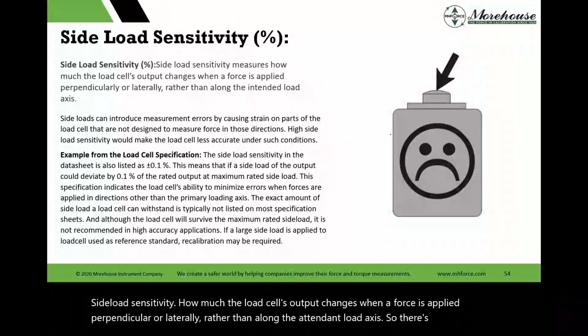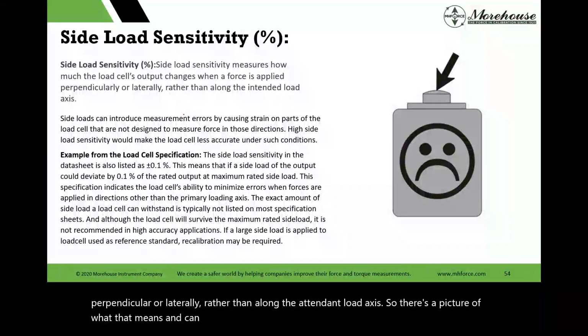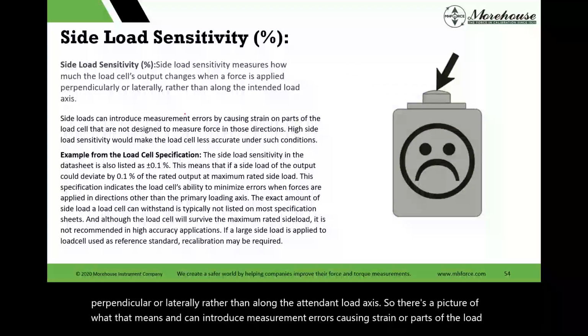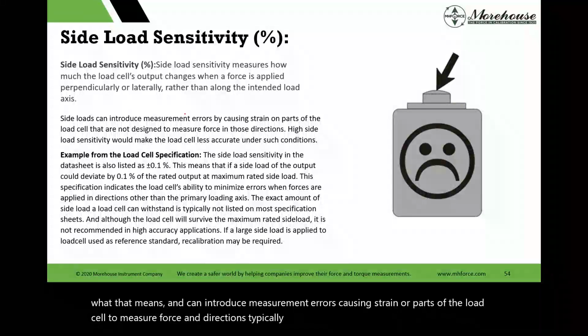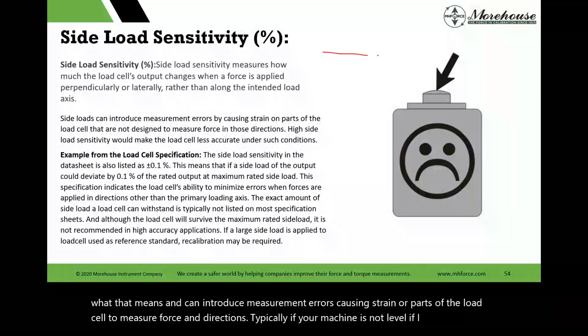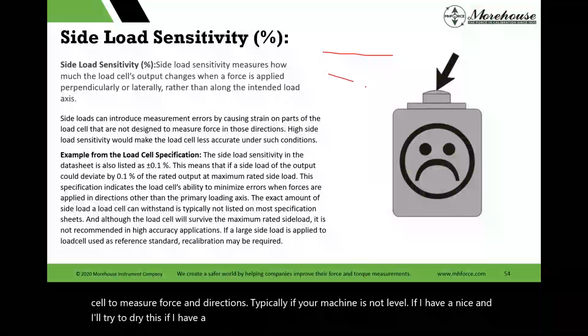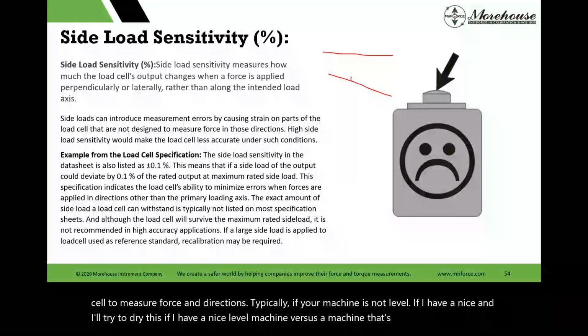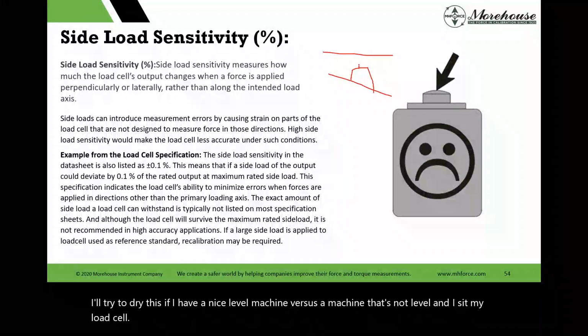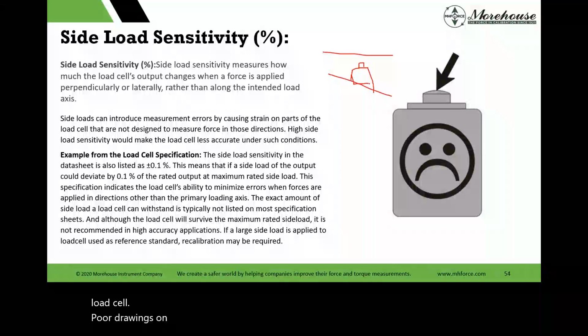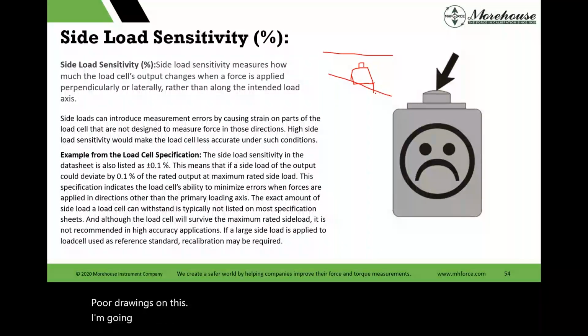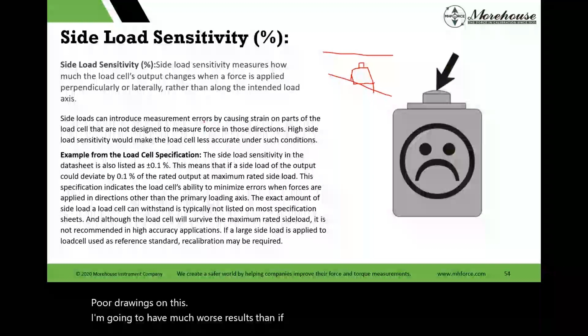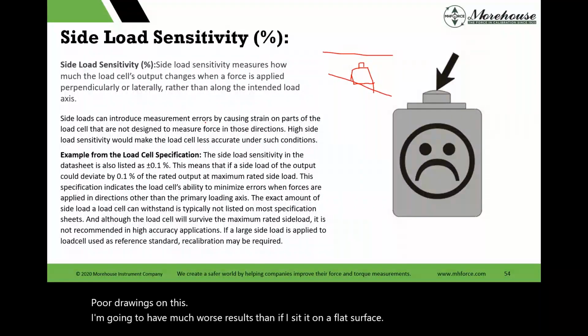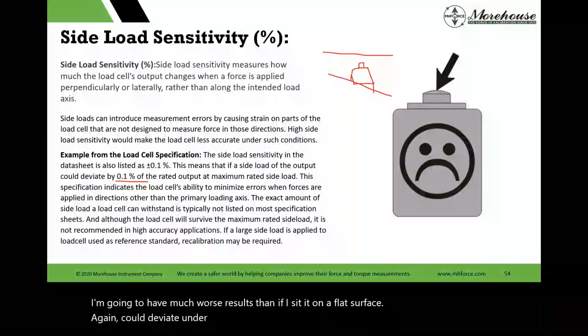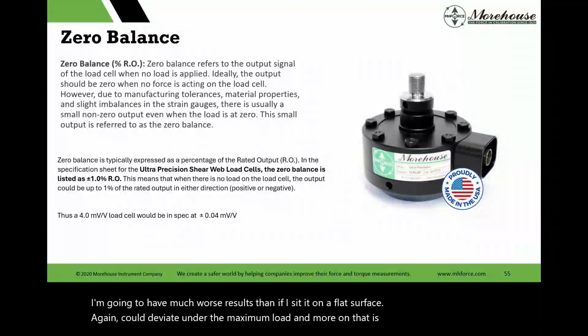So there's a picture of what that means, and it can introduce measurement errors, causing strain on parts of the load cell to measure force and directions. Typically, if your machine is not level, if I have a nice level machine versus a machine that's not level, and I sit my load cell, poor drawings, on this, I'm going to have much worse results than if I sit it on a flat surface. So again, it could deviate under the maximum load, and more on that is in that specification sheet.